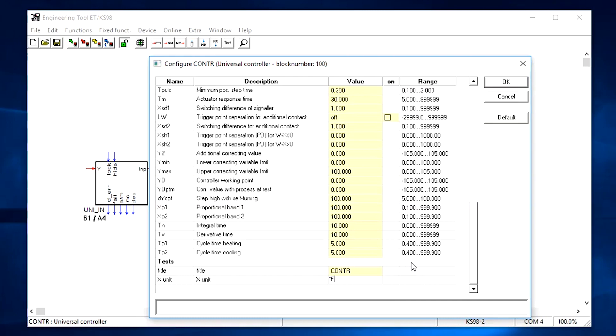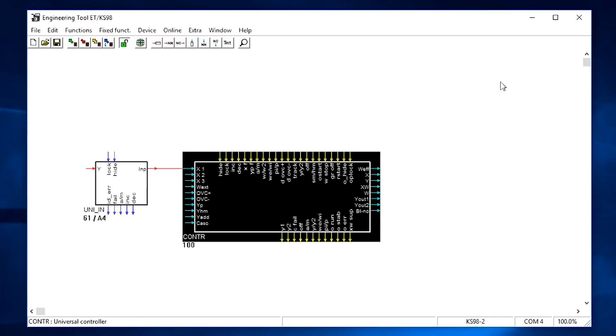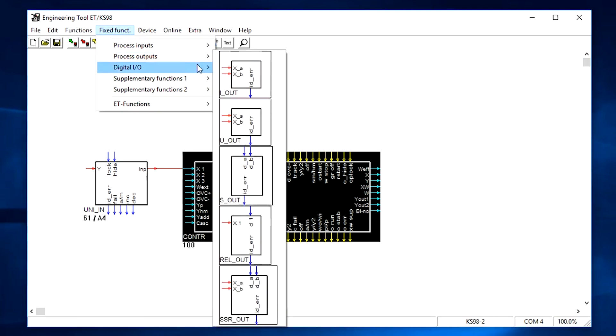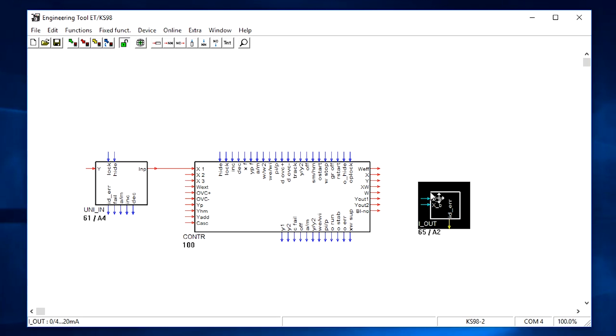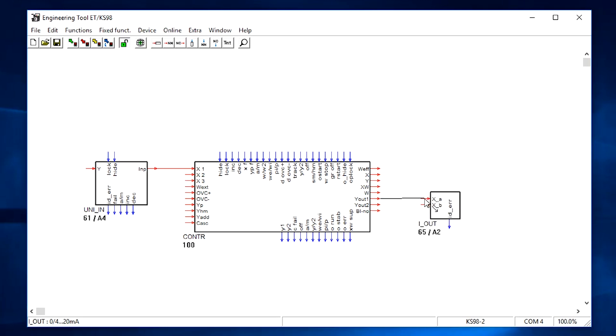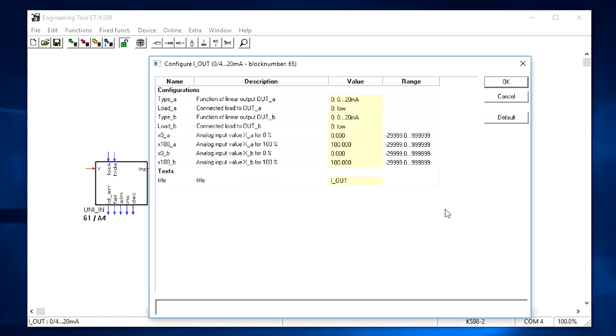Don't be overwhelmed by the number of parameters. Most applications can use the default settings, but for users with more specific needs the options are all available. With continuous control type you will need to use the analog output. For example we will use a 4 to 20 milliamp signal to a power controller. Go into the fixed functions and process outputs, select the current output block and place it on the screen. This needs to be connected to the first output from the controller. Double click to open the properties and set linear output to 4 to 20 milliamps.